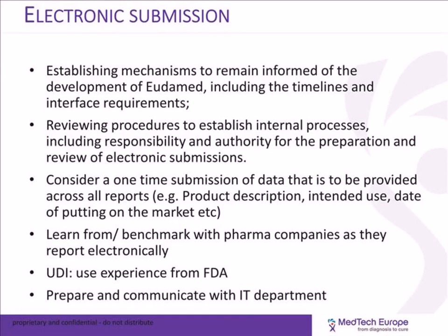The solution is in part built into the medical device regulation. If you look at Article 120 on transition and 123, until EUDAMED is ready, and EUDAMED may be late, the relevant provisions on exchange of information, including vigilance reporting, will follow those of the directives.